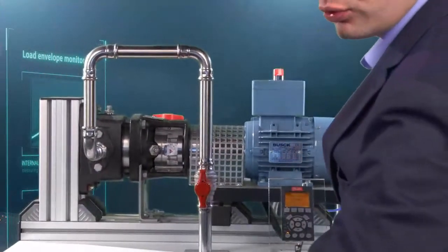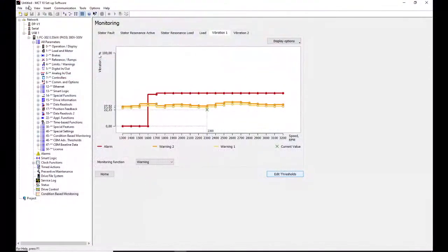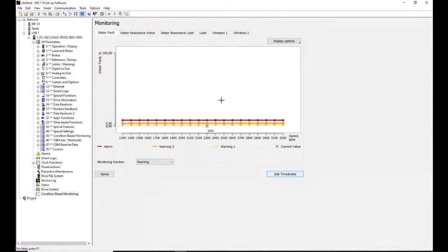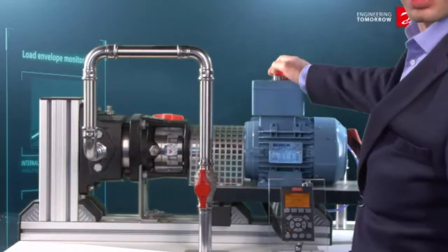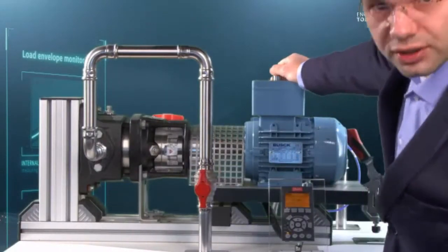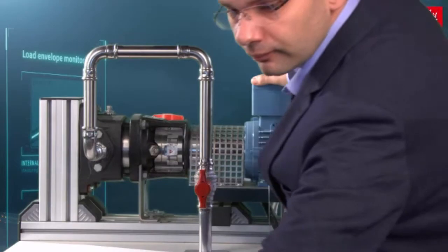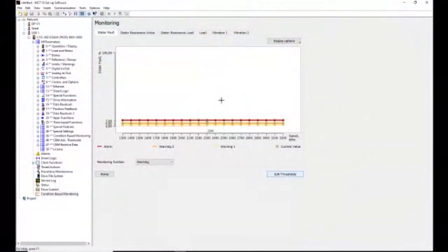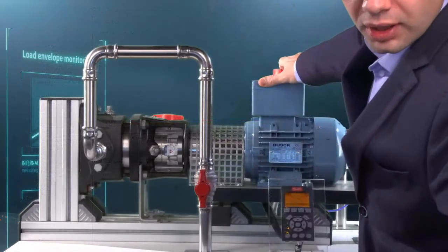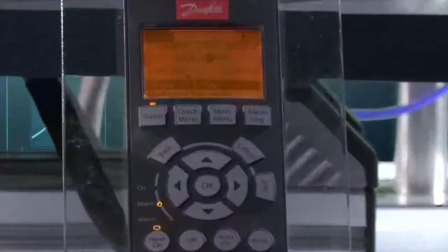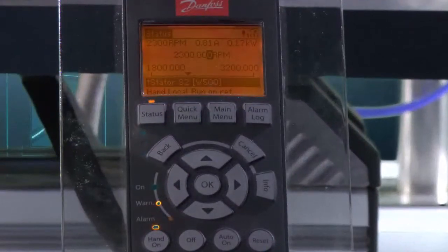Similarly, if we now go to stator monitoring, I create a fault by closing the switch, and then you can see the level exceeds the threshold, and the drive provides a warning on stator winding.